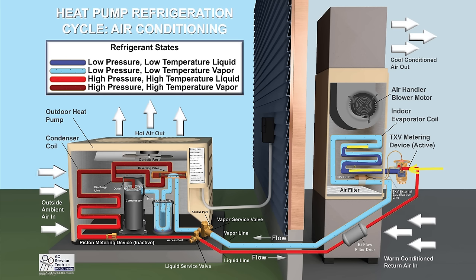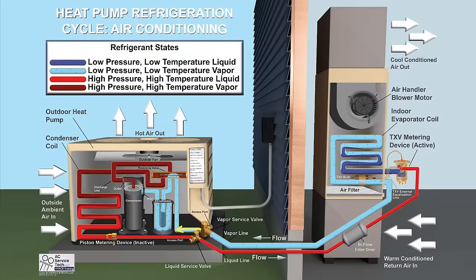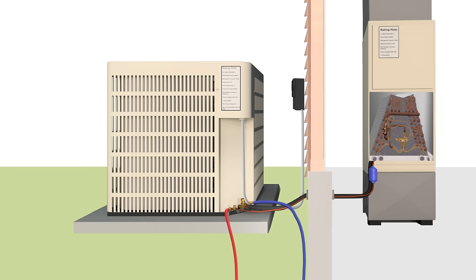The job of the coil is heat transfer between the refrigerant traveling through and the air crossing it. The air contains heat from within the building that you're trying to absorb into the refrigerant flowing through the tubes. The refrigerant then travels to the outdoor unit, goes through the compressor, increases in pressure and temperature — high enough that the refrigerant in the outdoor coil is warmer than the outdoor air, even on a 100-degree day.